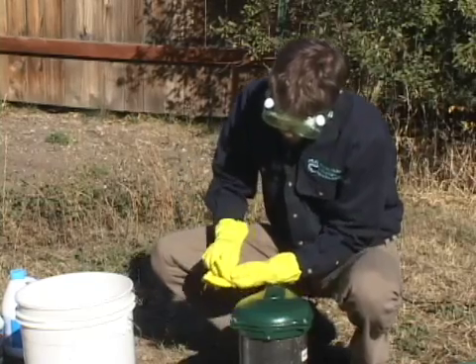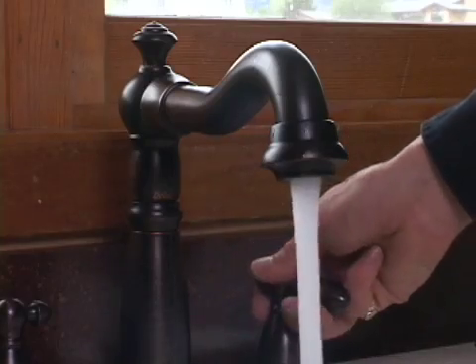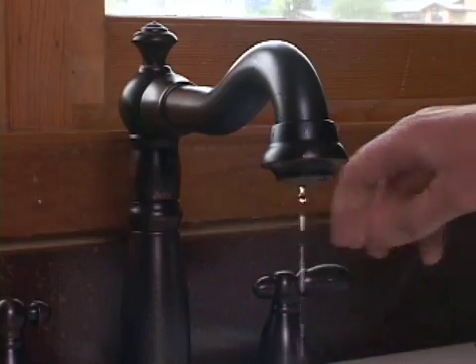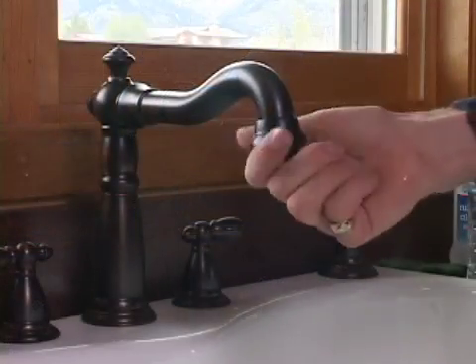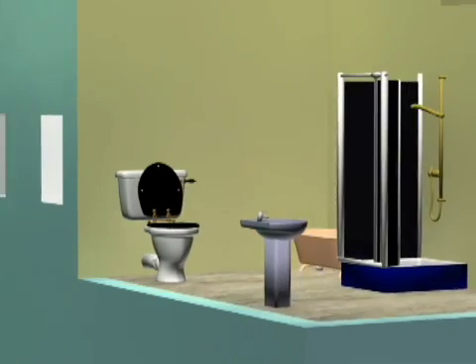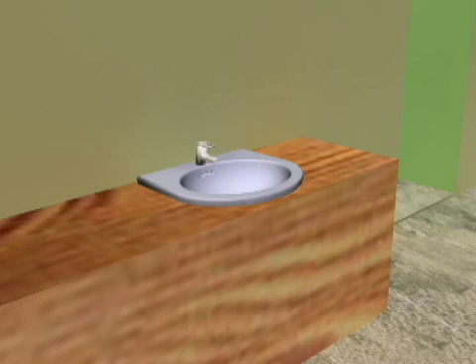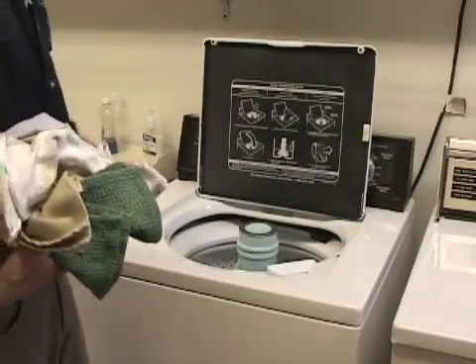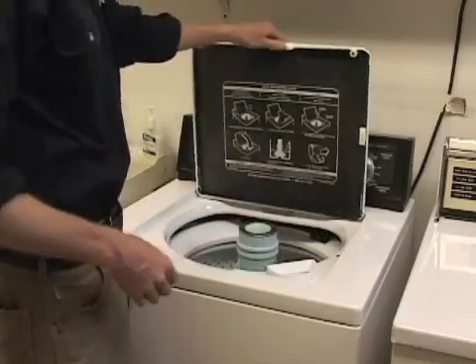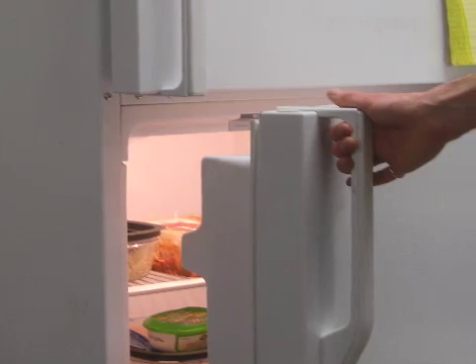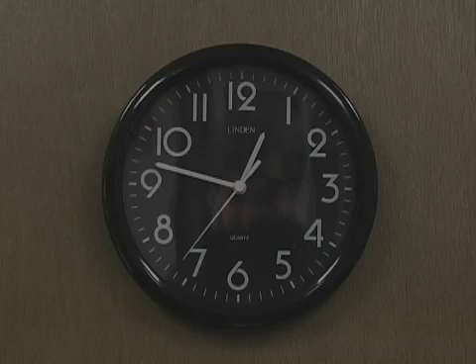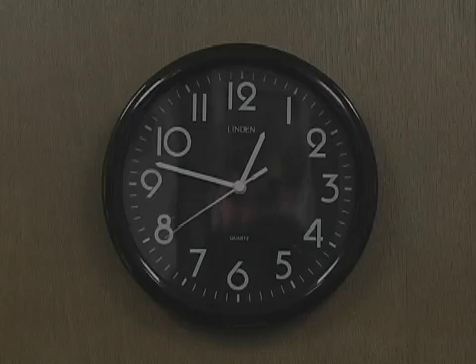Next, go to the faucet in the house that is furthest from the well and run the cold water until you smell chlorine. Turn off the cold water and do the same thing with the hot water. Remove screens from the faucets so they don't get clogged with debris broken loose by the chlorine. Now go to each of the faucets in the house and do the same thing. If you decide to chlorinate the lines to the washing machine, you may not want to run the water into the machine because there are screens that can easily be clogged by the debris loosened by the chlorine. If you decide to run chlorinated water into the drinking water lines for your refrigerator, check manufacturer recommendations and remove any filter or treatment devices associated with the fridge. Now let the chlorine sit in the lines for at least 8 hours, and preferably 12 to 24 hours.